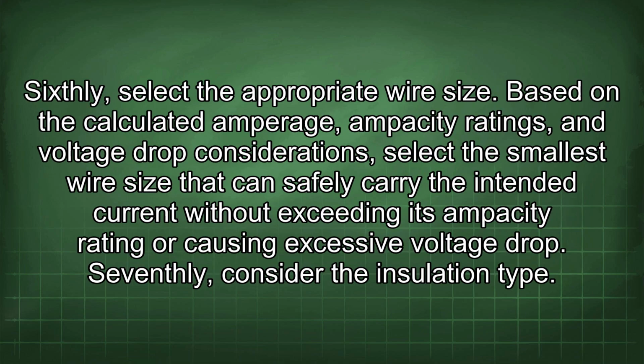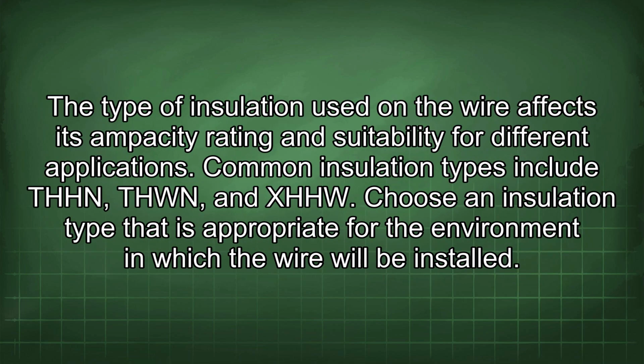Sixthly, select the appropriate wire size. Based on the calculated amperage, ampacity ratings, and voltage drop considerations, select the smallest wire size that can safely carry the intended current without exceeding its ampacity rating or causing excessive voltage drop. Seventhly, consider the insulation type. The type of insulation used in the wire affects its ampacity rating and suitability for different applications. Common insulation types include THHN, THWN, and XHHW. Choose an insulation type that is appropriate for the environment in which the wire will be installed.